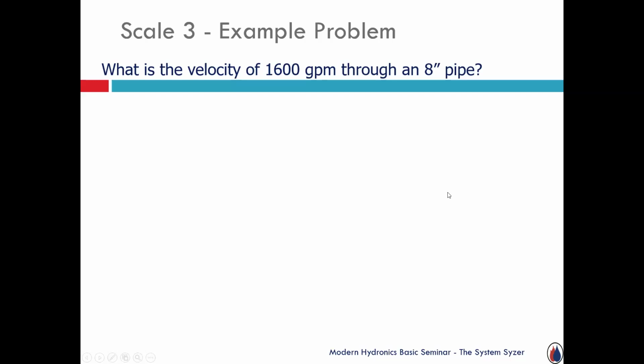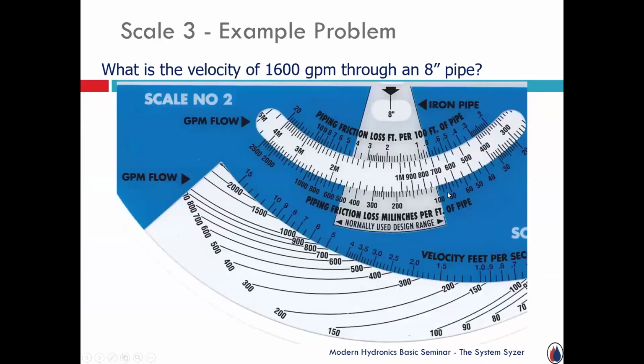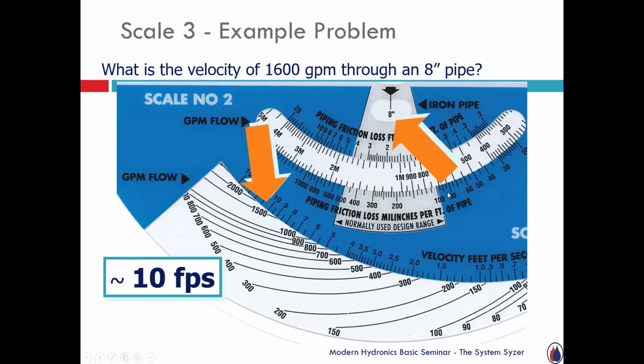Here's a quick question. What's the velocity of 1,600 gallons a minute moving through 8-inch steel pipe? What am I going to do? I'm going to go to scale 2 and line up 8-inch pipe. Then I'm going to look down to scale 3 and find the flow rate of 1,600 gallons a minute. Here's my 1,500 gallons a minute, there's my 2,000. Somewhere in between, obviously closer to the 1,500, I'm going to see where it intersects. It's probably about 10 feet per second. That's more than what the industry standards would say, which is to try to keep it at 8 or less. So they might say, let's pick another size pipe.